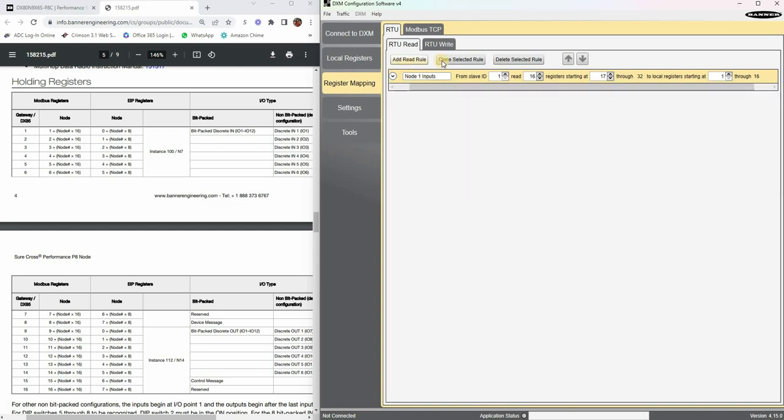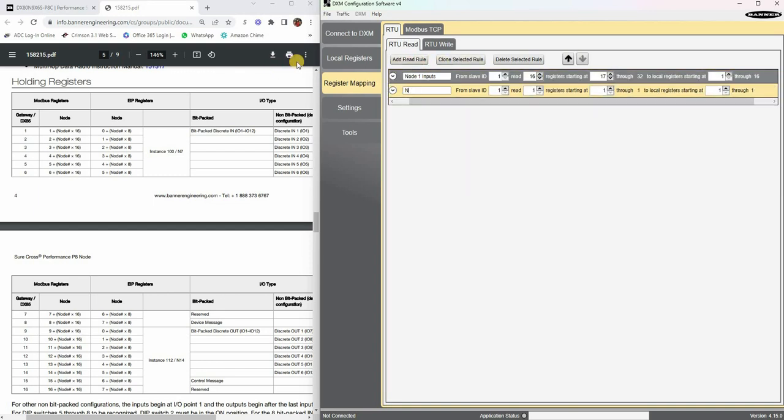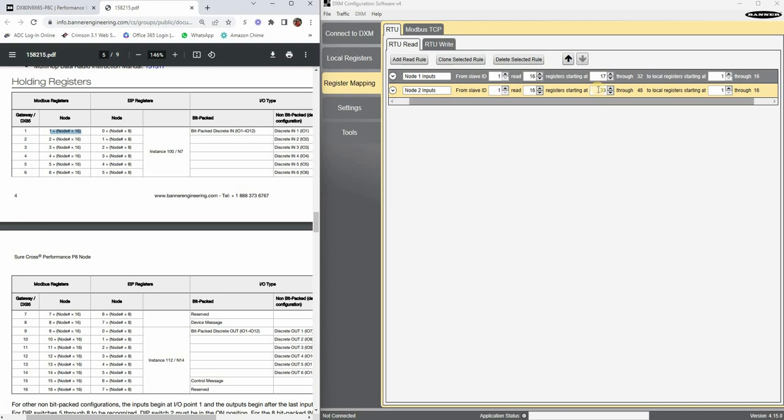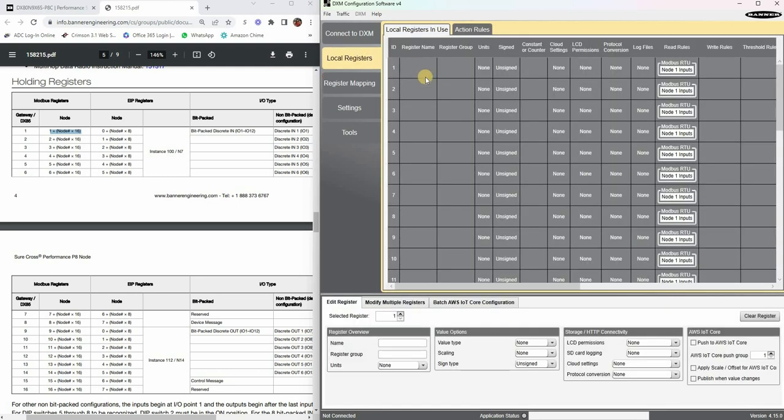Let's do one more read rule and we're going to call this node 2 inputs. Again, from slave ID 1. Again, we're going to read 16 of those. And this time they are starting at 33. Why? Because we're on node number 2. If you look at that formula, 2 times 16 is 32 plus 1, that's 33, that's where it starts. So we want to start at holding register 33, and then we're going to copy this to local register on the processor board. We'll start at 17 just to keep it consecutive here on my memory map. So this is done, this is what I need to do for my PLC to read something.